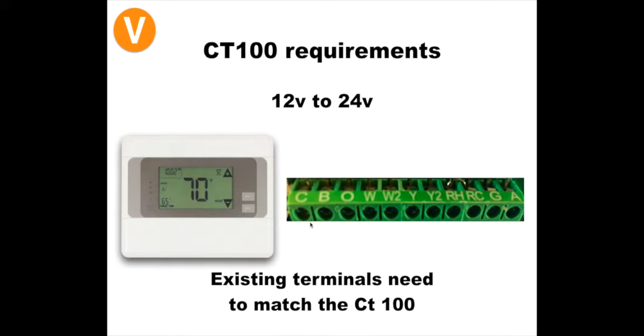Another requirement for this thermostat is you need to make sure the customer's original thermostat terminals match the terminals on the CT100. So if you look here, we have our CT100 terminal strip. We want to make sure that the customer's terminals are matching those. If we start to see terminals that don't match or terminals we've never seen before, it's always a good idea to either call your head tech or call myself, and we can confirm if this is going to be a system we can take over or not. But also make sure you use your tech binders, and experienced technicians also have a lot of knowledge on this. So try to utilize all the tools that we have out there. So voltage and the terminals need to match. Those are the requirements for our thermostat to be taken over.